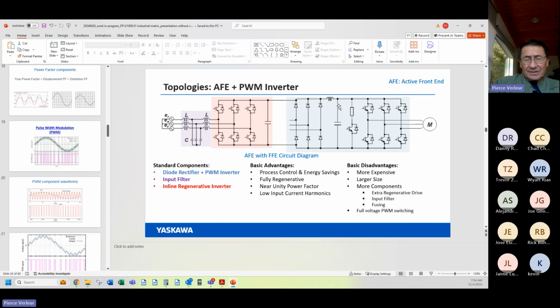They're not gigantic batteries. These capacitors are not there to act as batteries to back up the motor when there's a power line dip or power line outage. They're not a UPS system. These capacitors are here as filter capacitors to smooth out the DC bus. They're sized to take out the ripple, which is plus or minus 20 volts on the DC bus once we go through the rectifier. So saying that they're here as a giant UPS battery bank to back up the motor is just patently false.